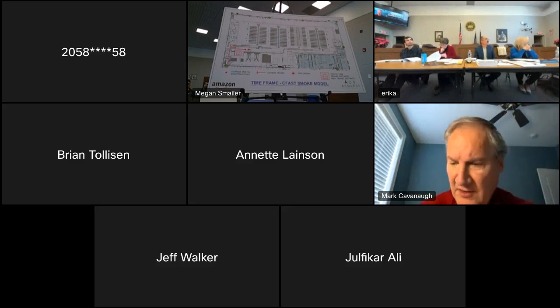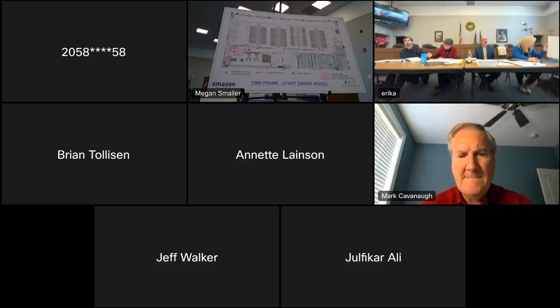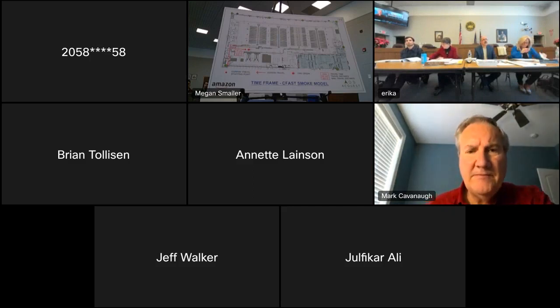I'm trying to understand the methods the fire department will use to extinguish a fire in there. Since it's a large building with long lays, and understanding its sprinklers, maybe an alternate might be to provide standpipes to help the fire department advance hose lines. I believe there are standpipes in the stair towers that go down into the parking levels. That is correct. But you don't have any standpipes on the floor itself? No.